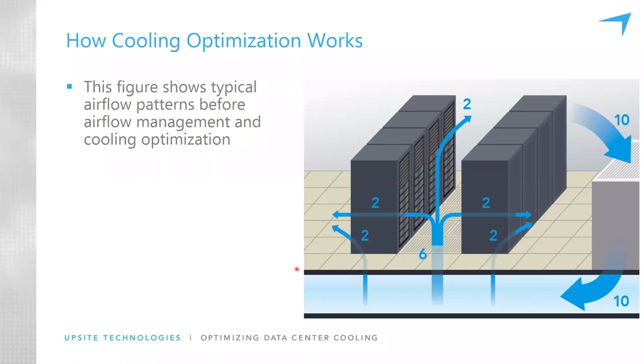And as long as the subfloor plenum is sealed, if you add up all the air coming out of all the holes in the raised floor, it's going to add up to 10. So in this case, we have 2 units of air coming out of unsealed cable openings under this row, 2 units of air coming out of unsealed cable openings in this row, and 6 units of conditioned air coming out of supply tiles in a cold aisle where it should. So 2, 8, 10 units of air coming out of the raised floor.